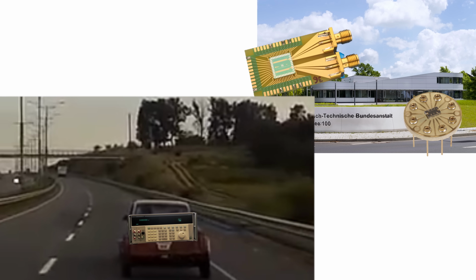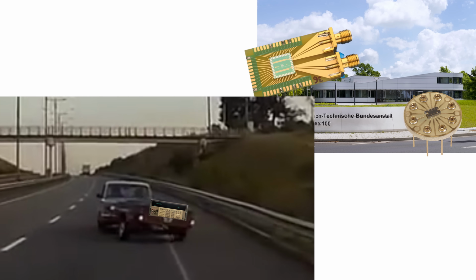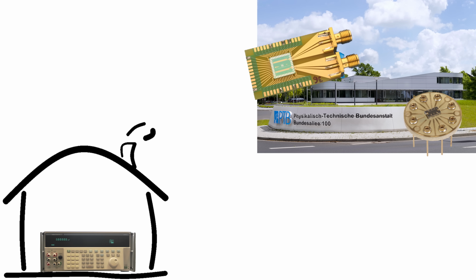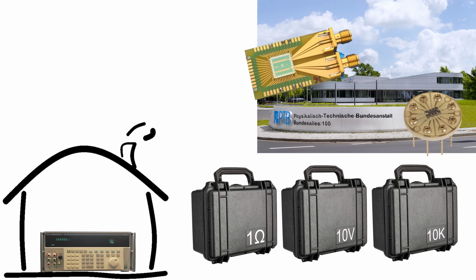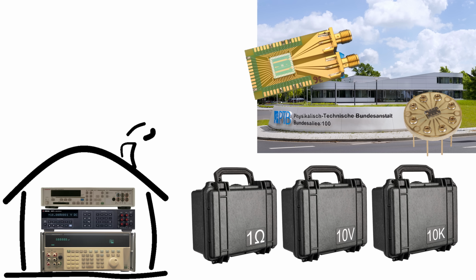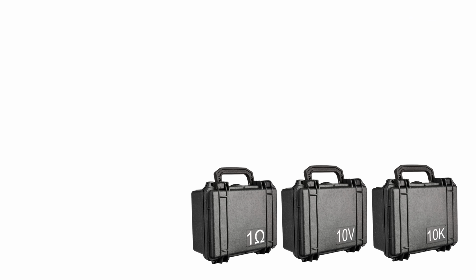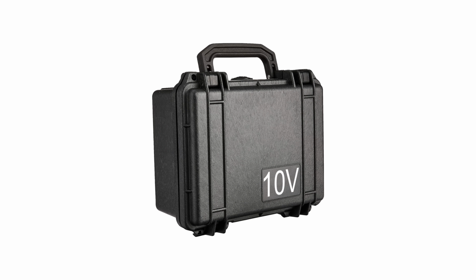Just from a logistics standpoint, it doesn't make sense to take the costly, heavy, fragile calibrator to such a primary standard in person, just to let it sit there for a day or two warming up, and then to lose half of the ppms on the way back home due to uncontrollable temperatures and vibrations. What we need are rugged traveling transfer standards with at least a good short-term stability spec, to import accuracy before handing over to Fluke and all other devices which happen to use the same artifact calibration principle. Today we are going to look at the 10 volt one. Or should I say, 2 different 10 volt approaches.